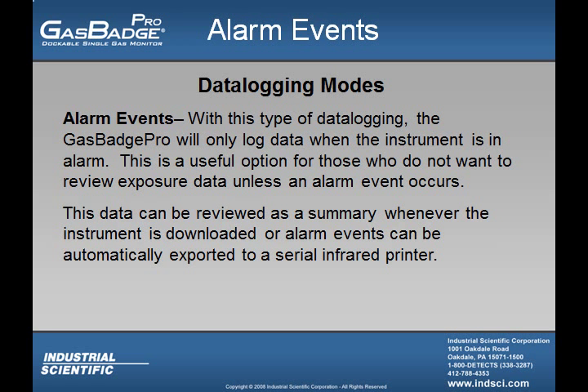With alarm events, the Gas Badge Pro will only log data when the instrument is in alarm. This is a useful option for those who do not want to review exposure data unless an alarm event occurs. This data can be reviewed as a summary whenever the instrument is downloaded, or alarm events can automatically be exported to a serial infrared printer. Both of these options are employed within the Gas Badge Pro continuously.